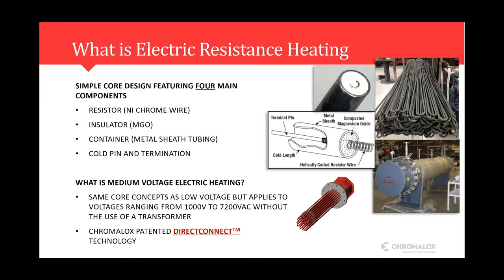And with that metal sheath tubing, inside of there, we make our cold pin and termination. And this is basically the same technology we use for all of our tubular element applications. And then on the other side, we also offer medium voltage technology. This is the same core concept as our low voltage, but we apply voltages from 1,000 volts up to 7,200 VAC without the use of a transformer. And that technology is called direct connect.